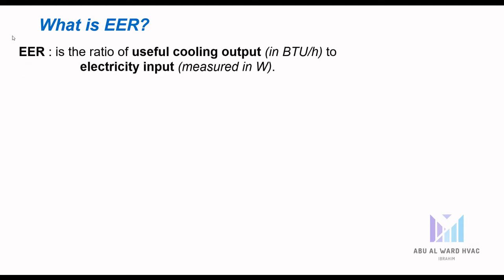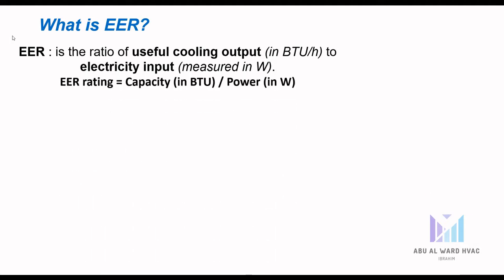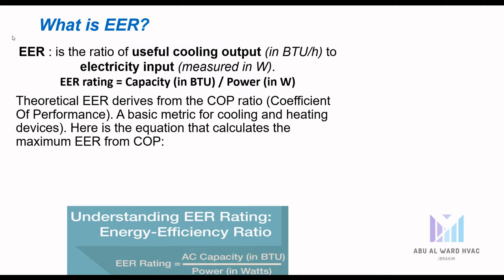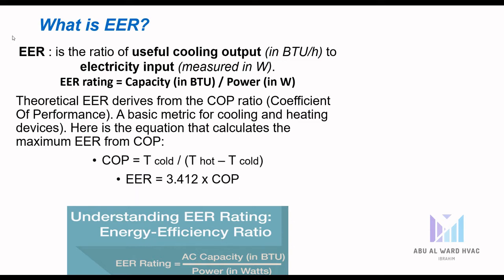The other consideration is the phase-out of some DX units to new technologies. Now, what is the EER? EER is the ratio of useful cooling output in BTU to electricity input measured in watts. The EER rating is capacity divided by power. In theoretical definition, the EER derives from the COP ratio as follows: COP equals T_cold divided by (T_hot minus T_cold).